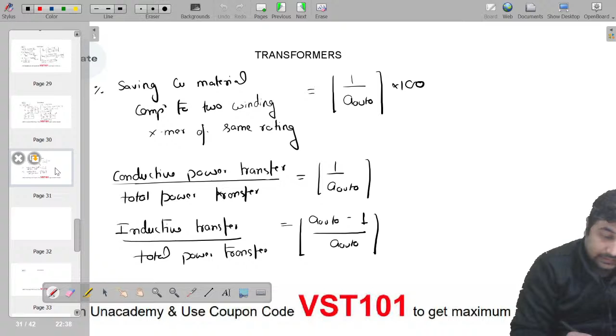So I am representing the fourth point here. Fourth point is kVA capacity of auto transformer compared to two winding transformer. In case the same amount of material is being used, then you can only use this formula for additive polarity, as A auto upon A auto minus 1 into 100. But this formula is only valid for additive polarity. Here I am representing, please see.